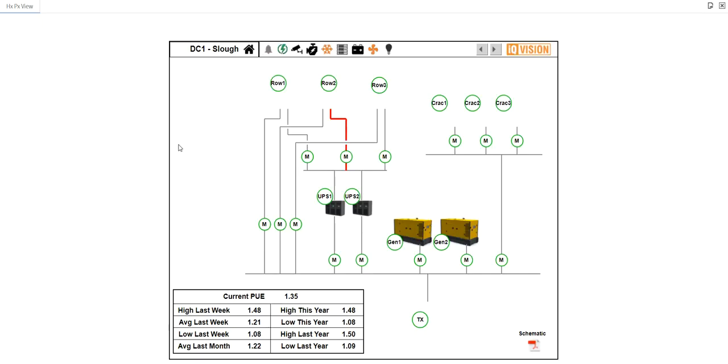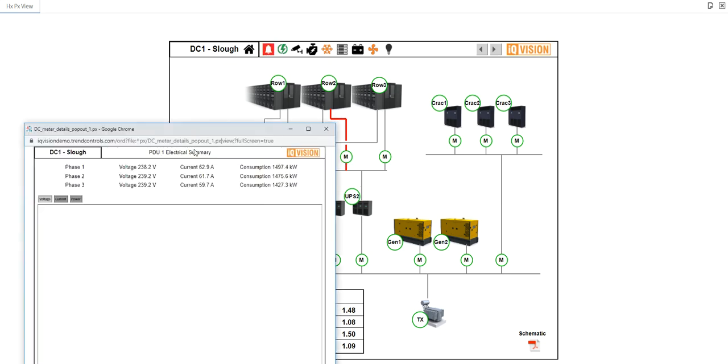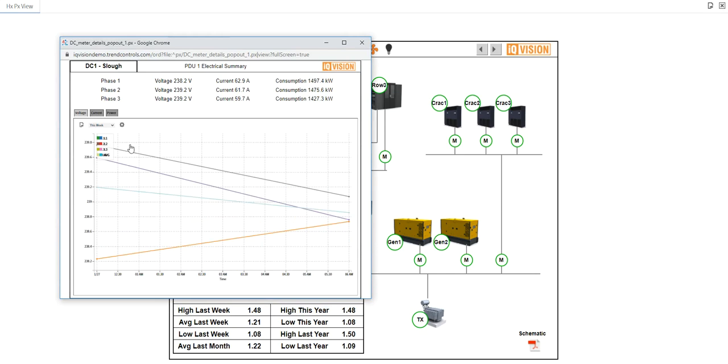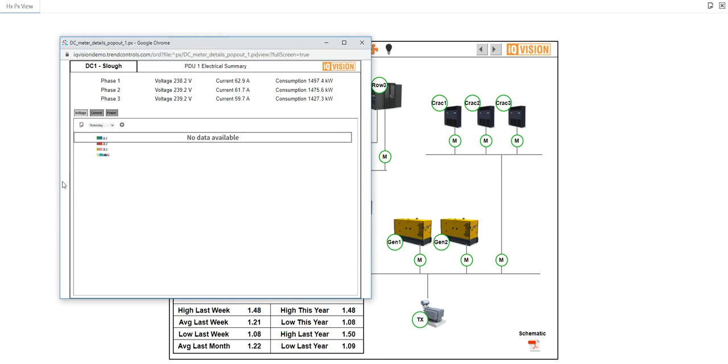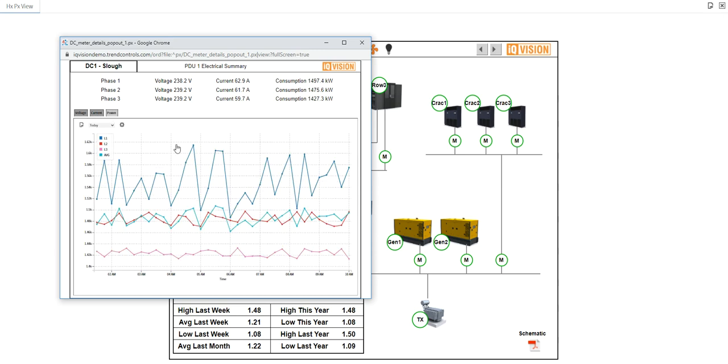If I go to some of the other overviews, we have an electrical overview, a very simplified electrical map of the data center. This is not complicated at all. I've put in some warnings here again in the same principle. Red is bad. We've lost one of our lines to row two. So one of the redundant supply lines from the breakers has dropped out. That's not a major problem. We have some details here as well. We can go in and look at all the supplies for today, this week. You can see it's averaged it all out, smoothed it from this week, yesterday and so on. Same for current and the same for power with a little summary at the top.